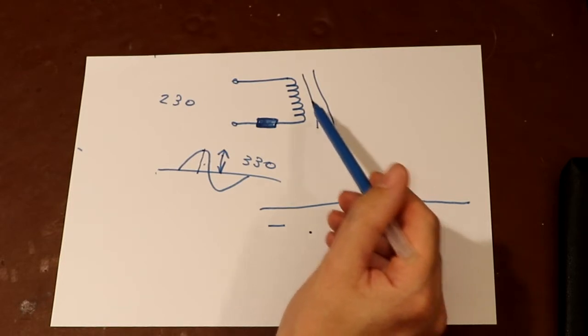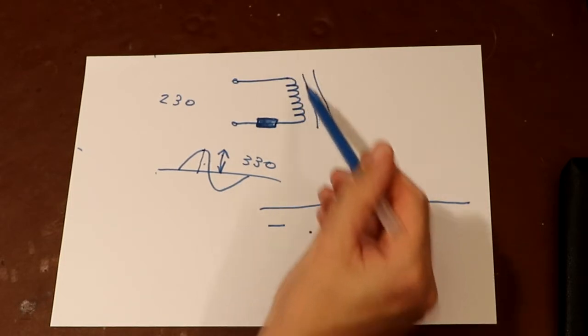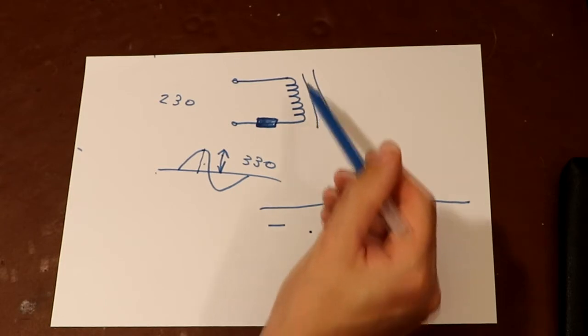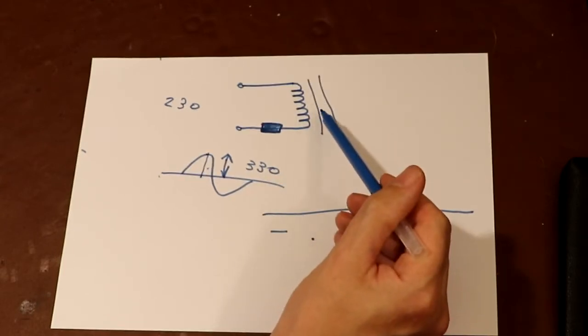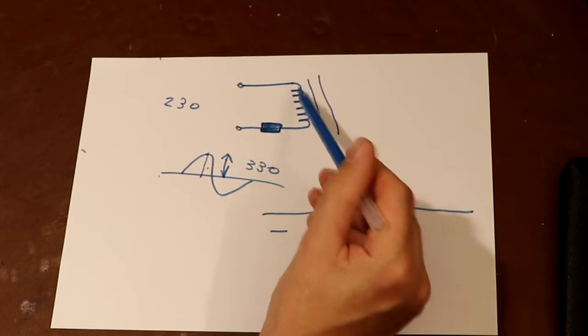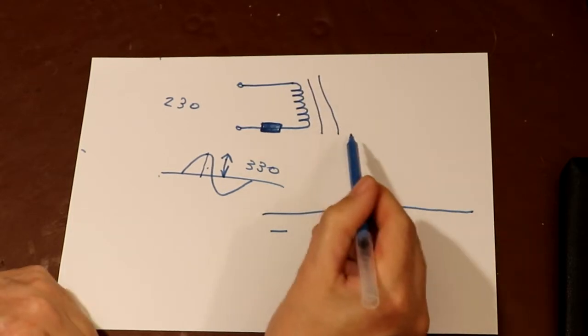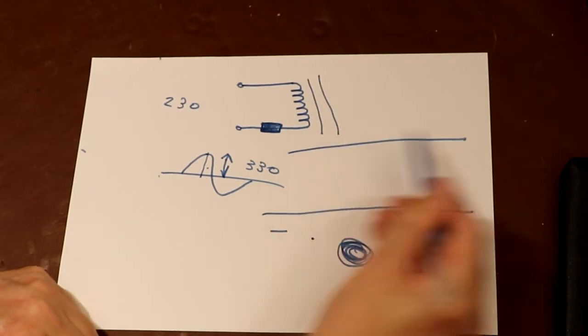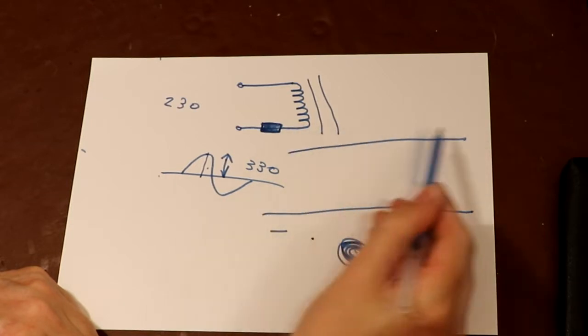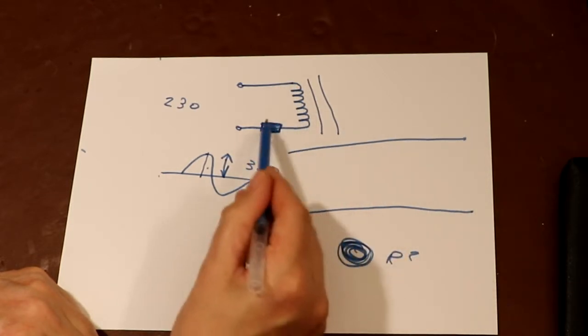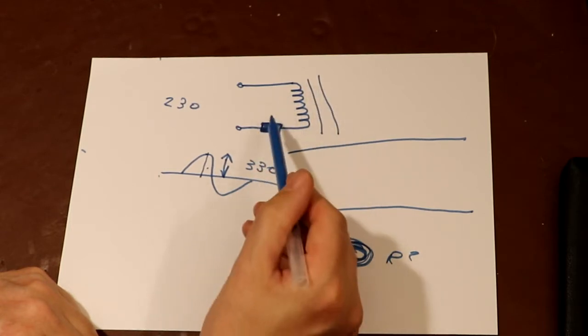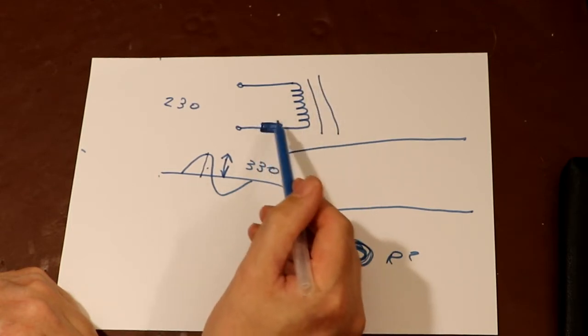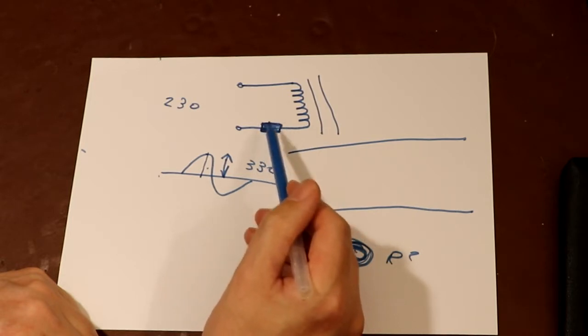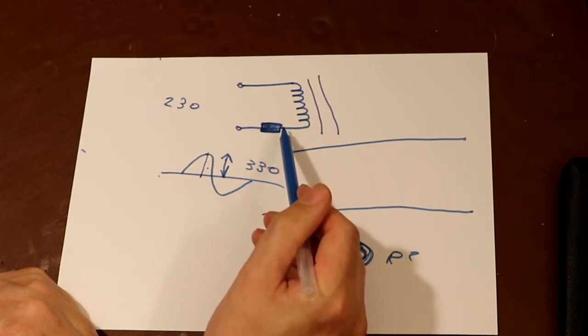So what's really happening is this isn't acting like a normal magnetic circuit—the transformer saturates. Rather than acting like a coil of wire, it just starts acting like a long piece of wire. The only thing limiting the current flowing in this now long length of wire is this resistance here. So at switch-on, the thing that really limits your inrush current is the DC resistance of your transformer coil.